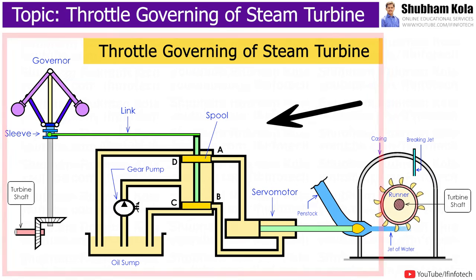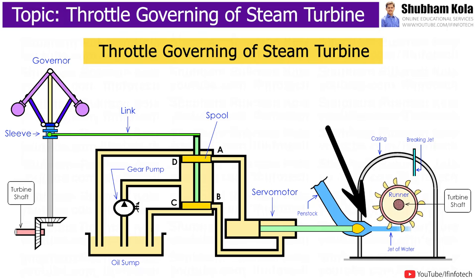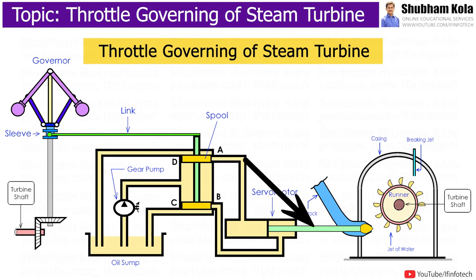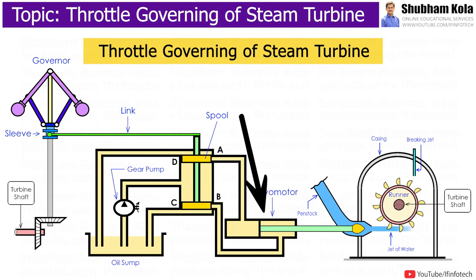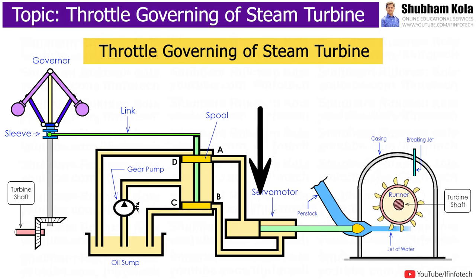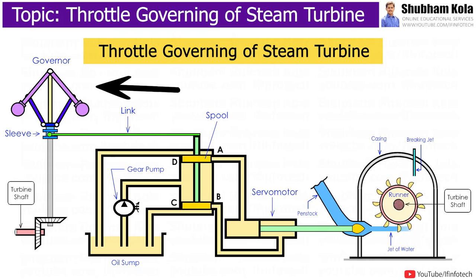In throttle governing, the pressure of steam is reduced and controlled before the steam reaches the turbine. The flow of steam entering into the turbine is restricted by a balanced throttle valve, which is controlled by a centrifugal governor. In the case of small turbines, the throttle valve can be actuated directly with the help of the governor through a linkage.